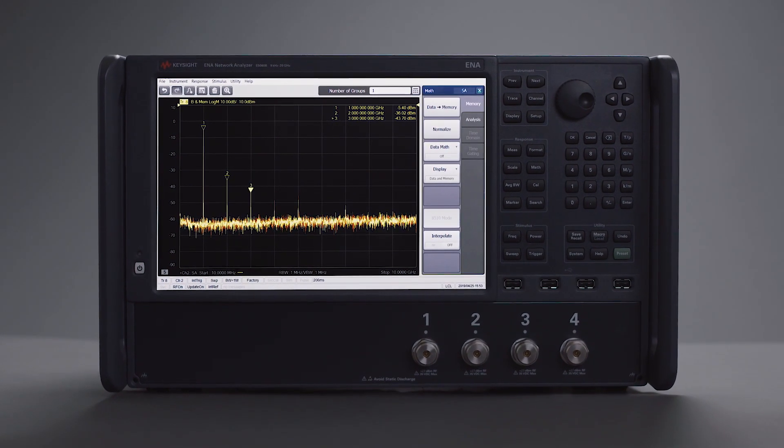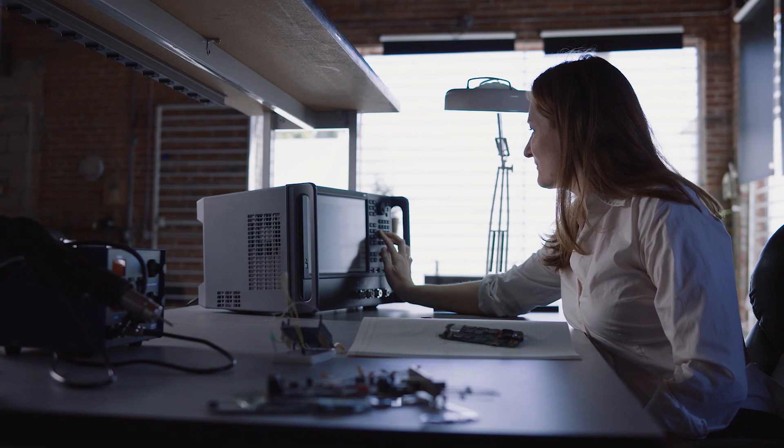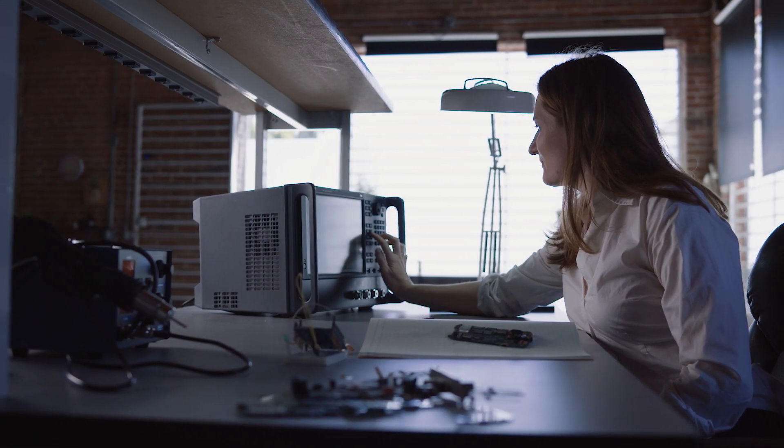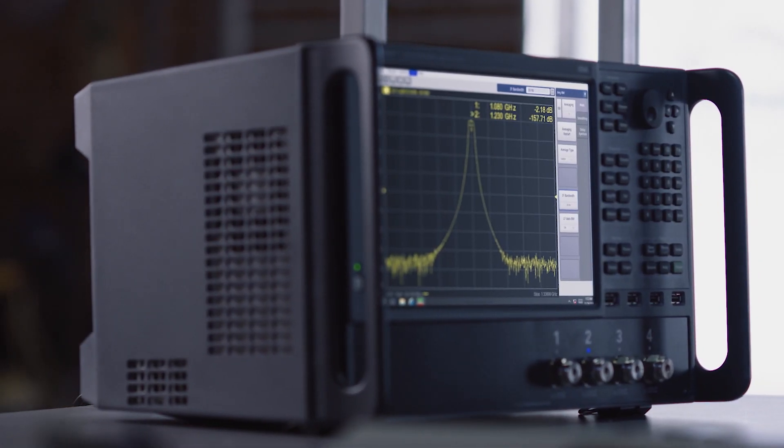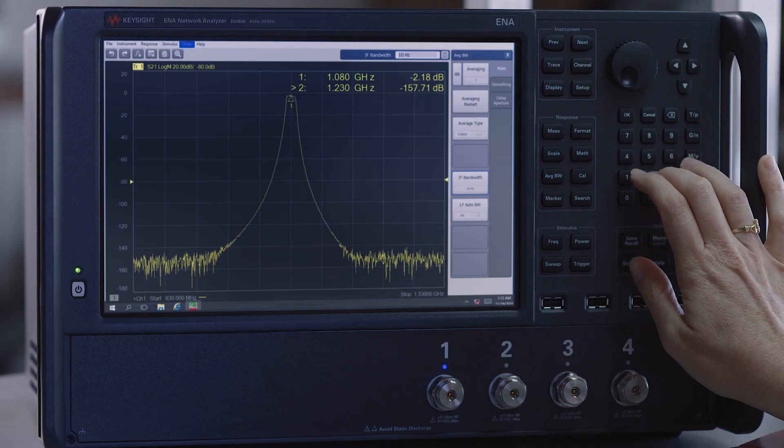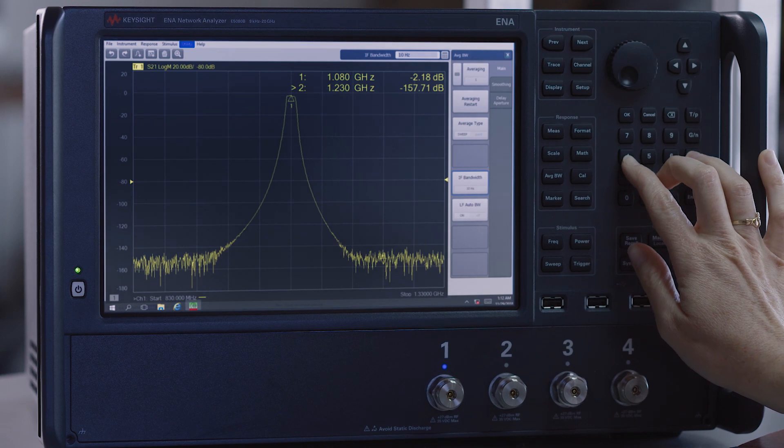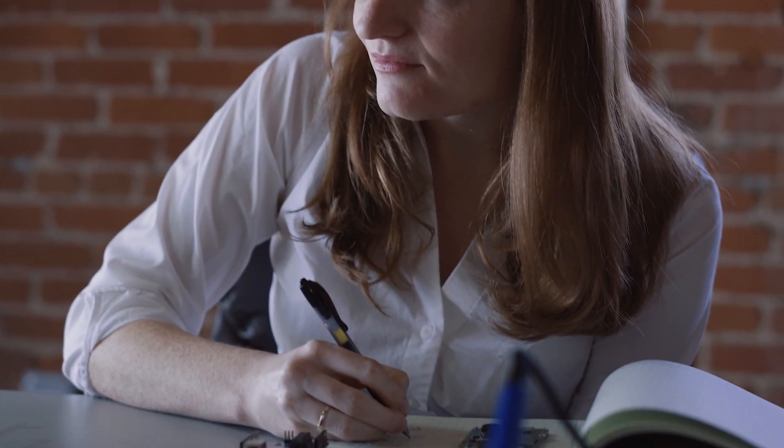The E5080B offers best-in-class dynamic range, so you can use wider IF bandwidth for faster measurements while capturing the full response of amplifiers and high rejection filters.